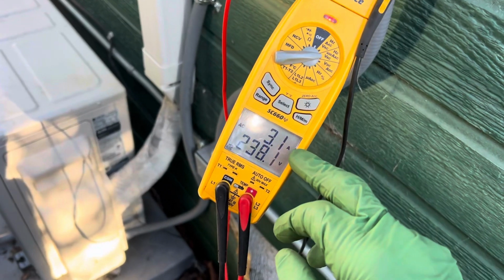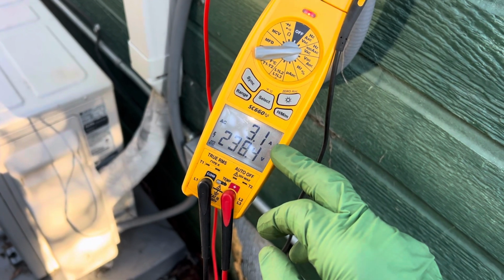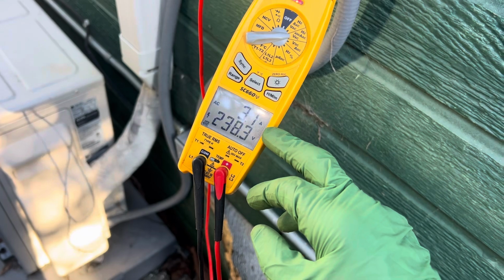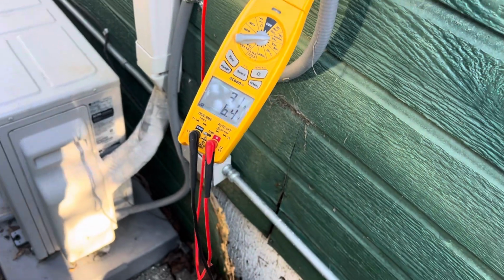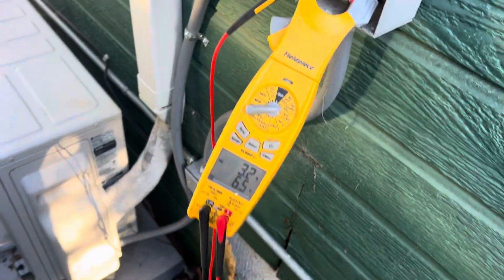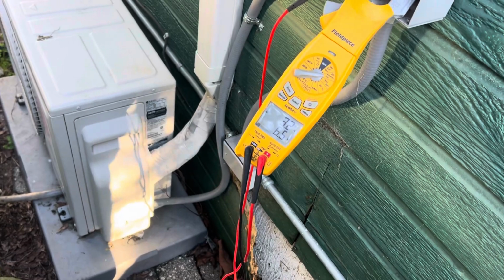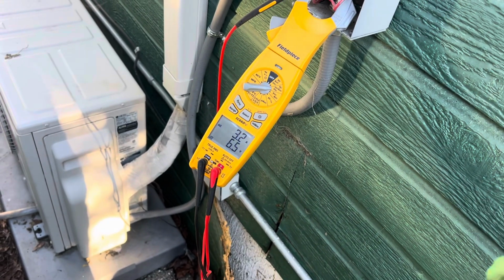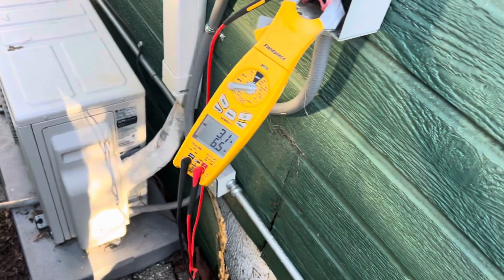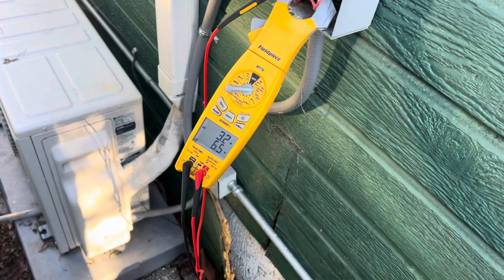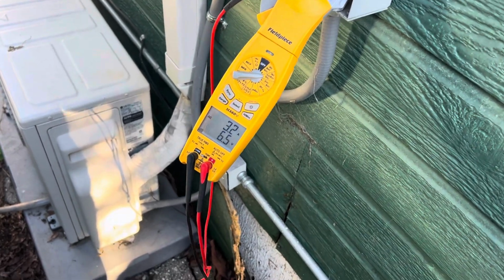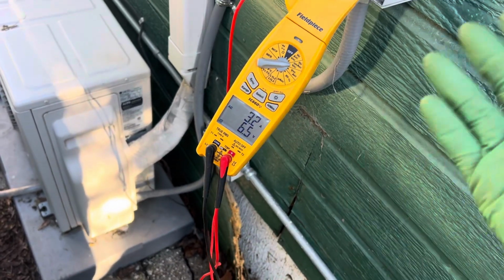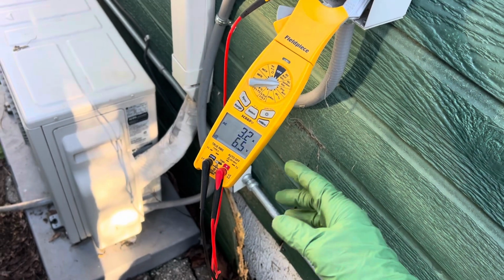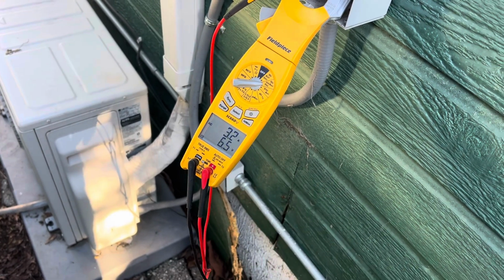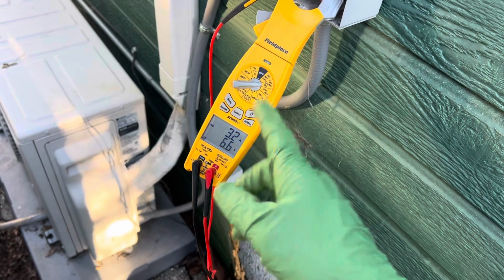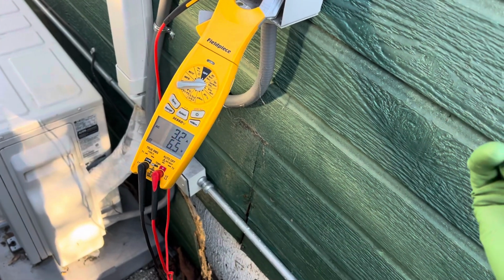As you can see, it's only drawing 3.1 amps from here. That's basically the maximum it'll ever draw, and it won't go any higher than that. This isn't North Dakota where it goes down to negative 15 below zero — we're in a place where it very rarely gets below freezing, usually in the 50s and 40s. So at 3 amps, it's impossible for this to blow a 15 amp circuit breaker.